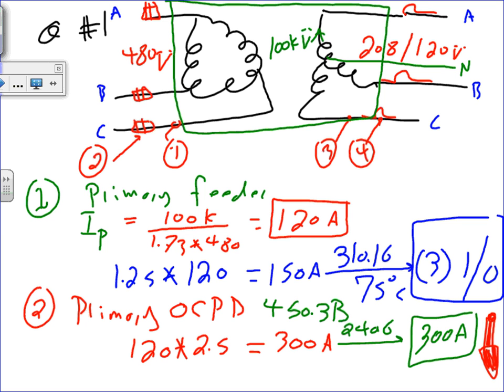So there are tap rules. We're not going to get to the tap rules, but you're good. Make sure that your fuses are not further than 25 feet away from the transformer, which is most of the time, guys. You bring the panel here, the transformer here, and the second panel here. So really not a big deal. Any question, guys, about the primary and the secondary? The primary overcurrent protection device? We're always using primary and secondary to size that, instead of using the top one from 450.3(B), for primary only.